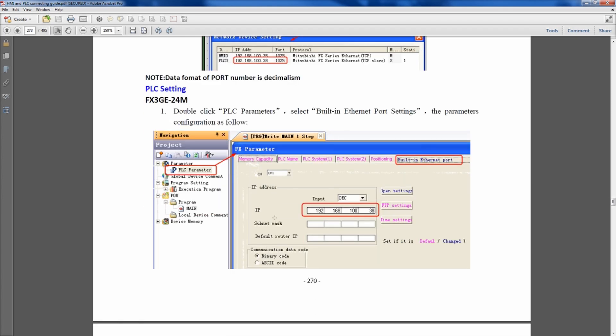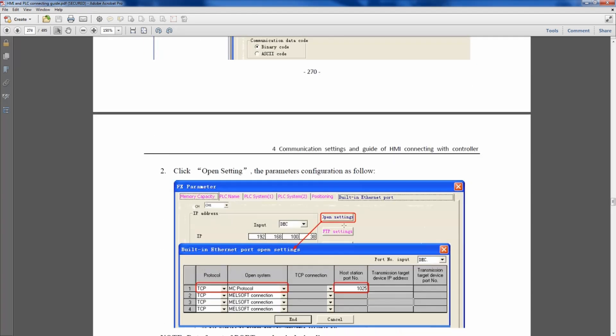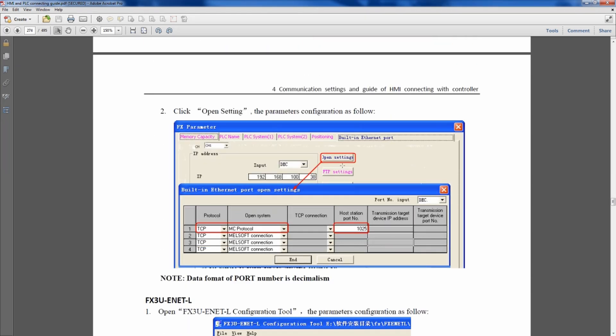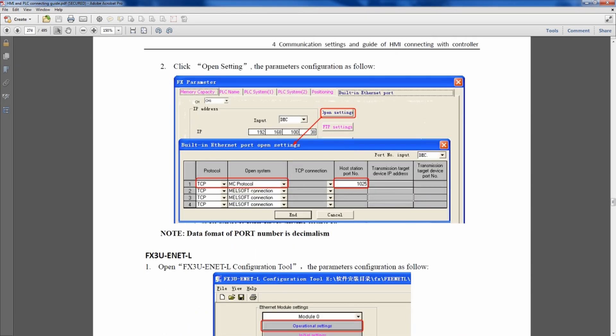Under Mitsubishi's PLC software, you're going to go to the project under the PLC parameters, set the IP address, and make sure you have the input set as decimal under this built-in Ethernet port tab. As you scroll through, you go into open settings, make sure you're using the MC protocol, not the Melsoft connection, and make sure the host station port number is 1025 as listed in the HMI software.